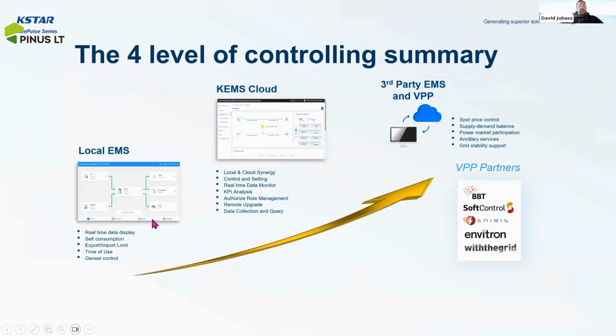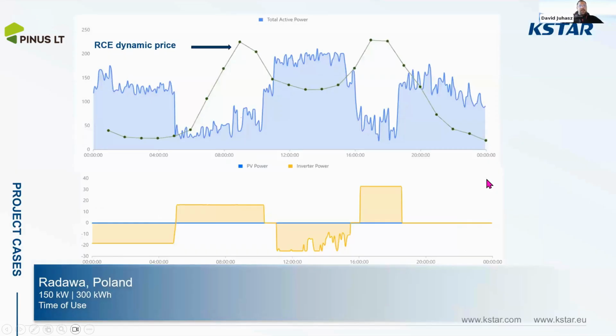So we talked about the local EMS, the monitoring platform, and the third-party EMS, and we have this fourth level, which is the VPP partner integration of that controlling, which can be done by the third-party EMS, and it makes possible the spot price control, the supply-demand balance, power market participation, and ancillary services, frequency control of our equipment to stabilize the grid. This is one example of the spot price control in Poland. When the prices are high, it starts to discharge, and when the prices are low, it starts to charge the cabinets, generating profit by discharging at the correct time.